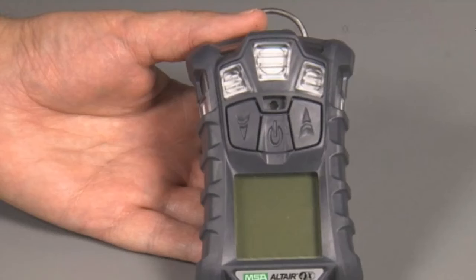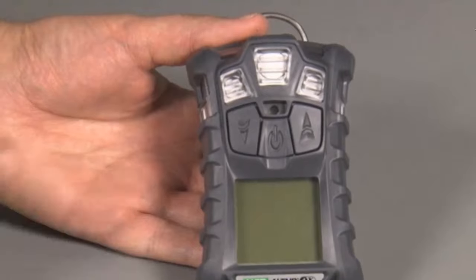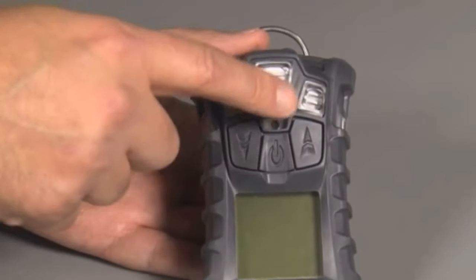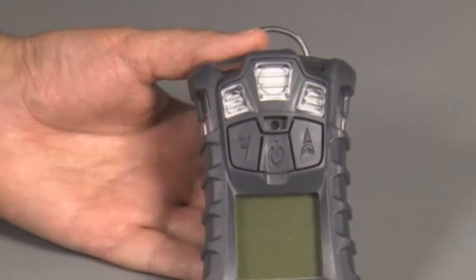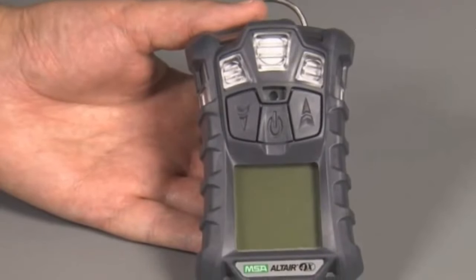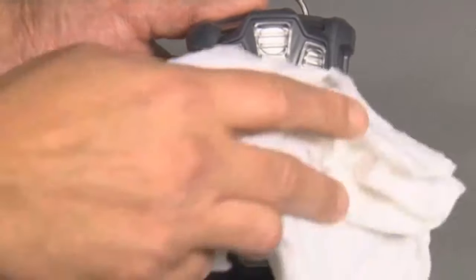The Altair 4X multi-gas detector requires very little maintenance. Always be sure that sensor and alarm openings are clean and free of debris. If cleaning the Altair 4X multi-gas detector is necessary, wipe the instrument with a clean, damp cloth. Do not use cleaning chemicals or soaps to clean the unit, as sensor damage may occur.